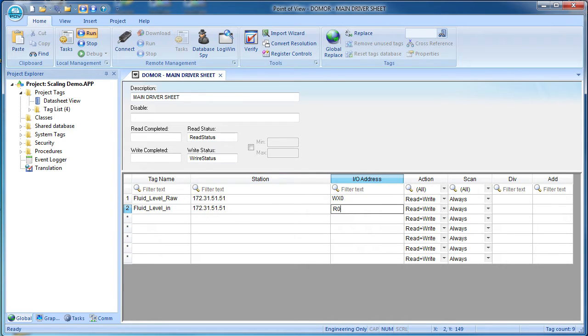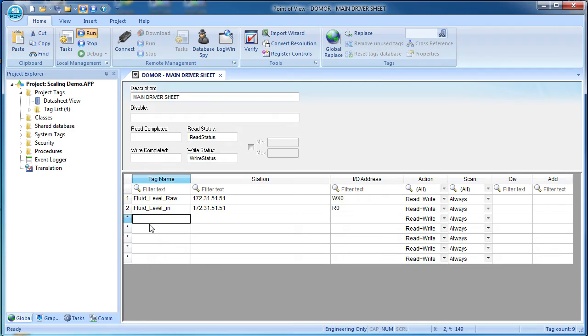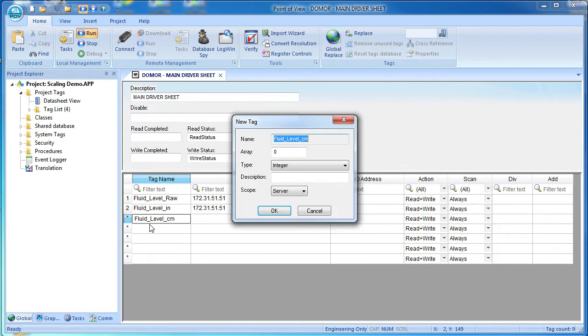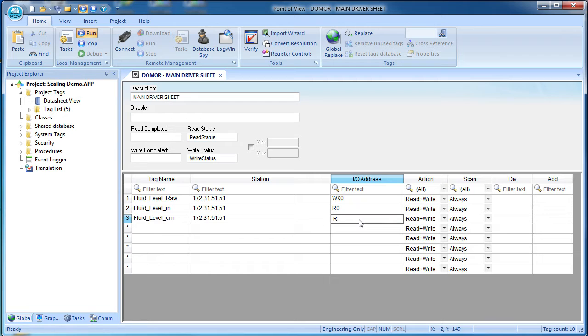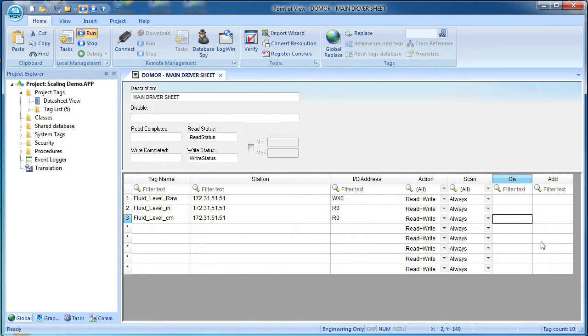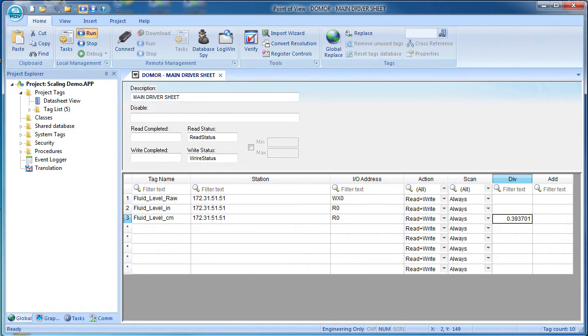And finally, let's create a tag to put Point of View's automatically converted result in. We'll call that fluid level centimeters – and that needs to be a real. Same IP address – and we want to convert that same inches value we brought in a minute ago. To convert inches to centimeters automatically in Point of View, we just divide the incoming number by this scaling factor and there is no offset so we leave this blank.